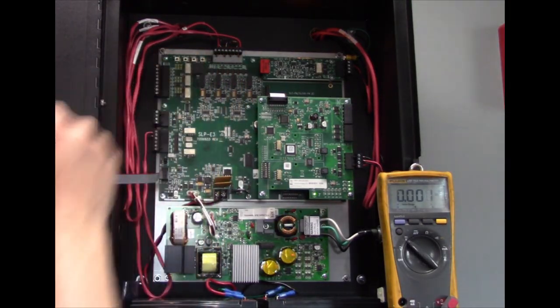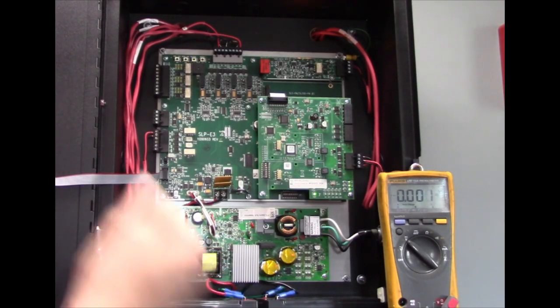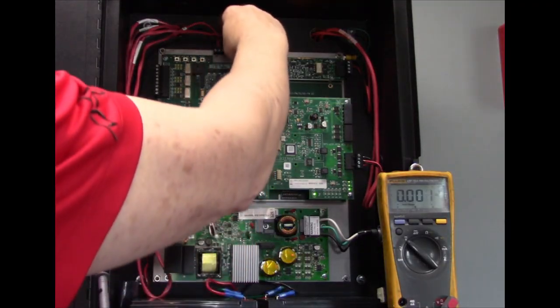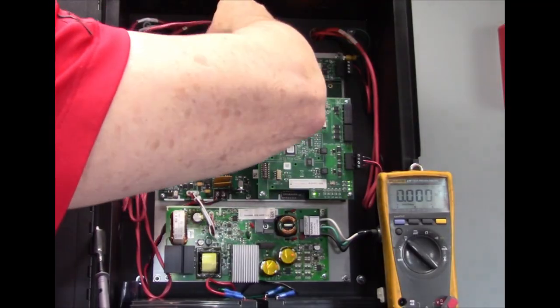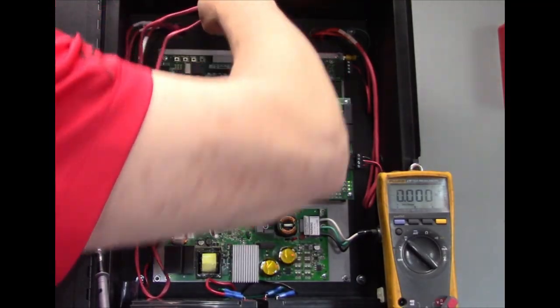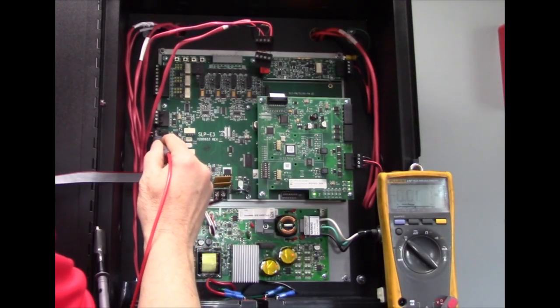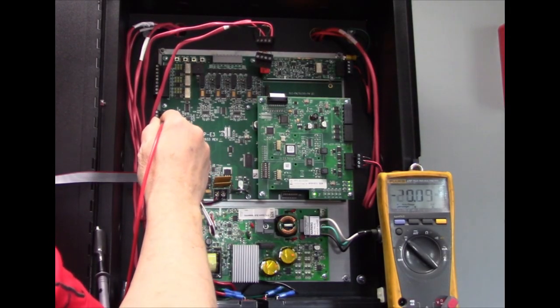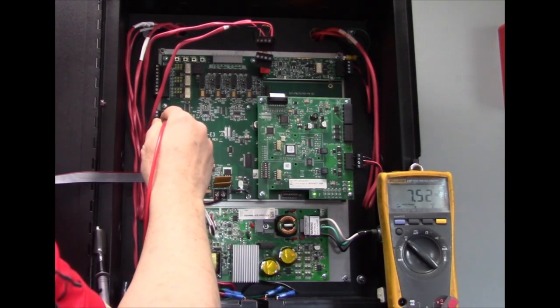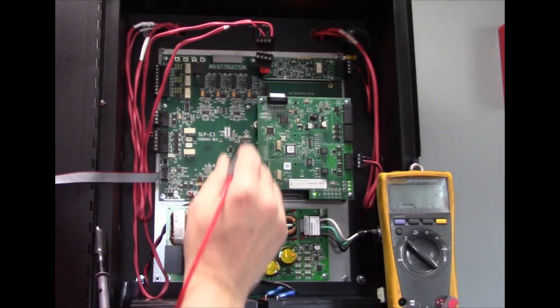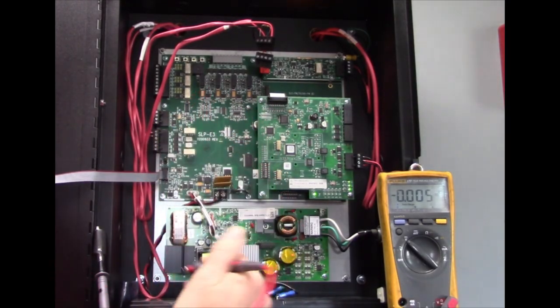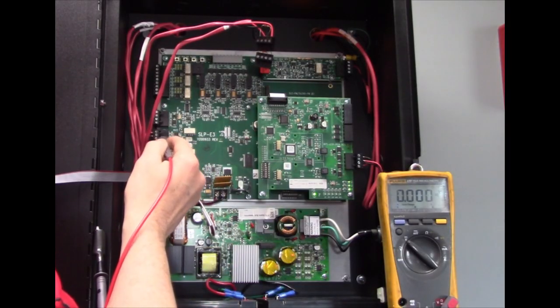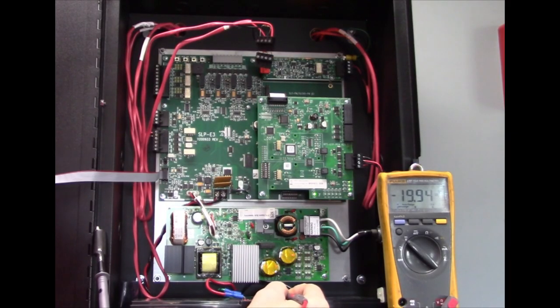Low hanging fruit. The notification circuits aren't going to any control modules or smoke detectors. They're just going to horn strobes, things like that. So we can lift these off the terminals. And we'll double check our voltage here. Still have 19 on the negative and 7-ish on the positive. So that's not it. I'm going to pull this circuit here. I need to find an alternate place to measure because I'll have the terminal board off. The battery negative is another place we can get that.